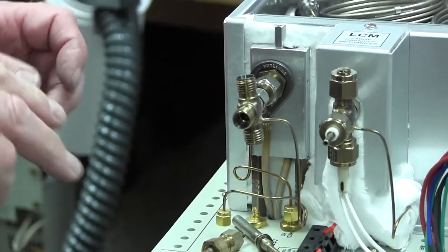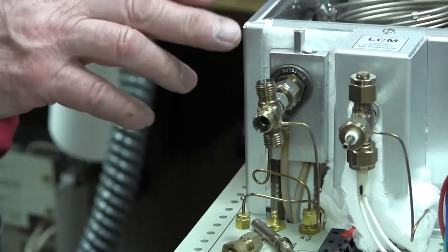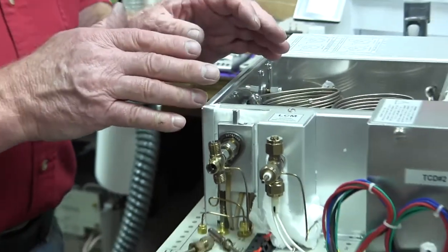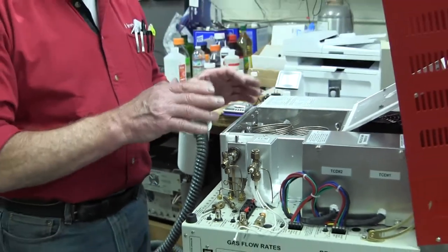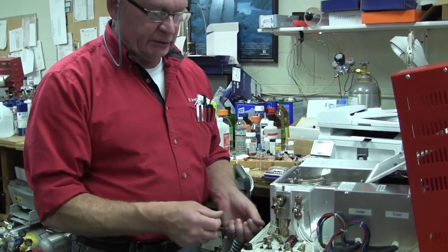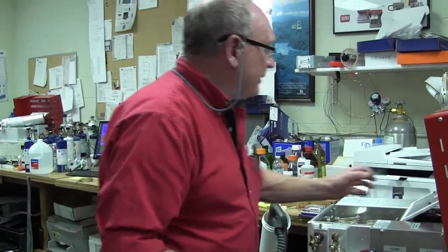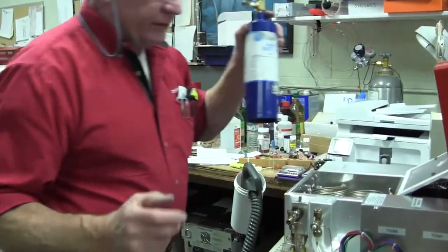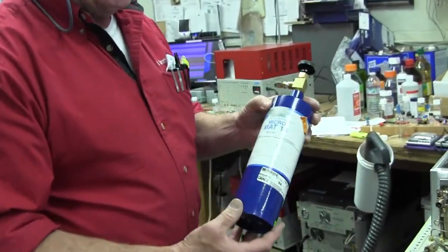You set that to 300 degrees, and if the methanizer is working perfectly, the carbon monoxide and carbon dioxide will give you the same size peak as a methane peak of the same concentration. Here we use a gas calibration standard that has 1% of methane, CO, and CO2.